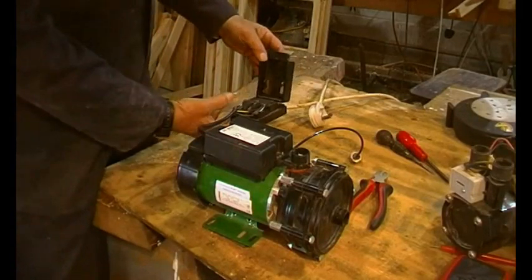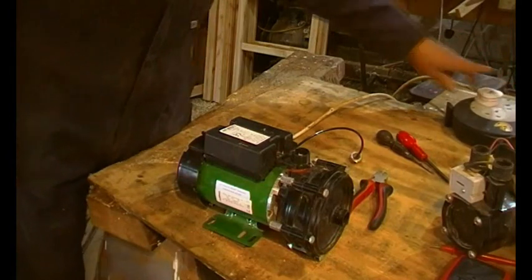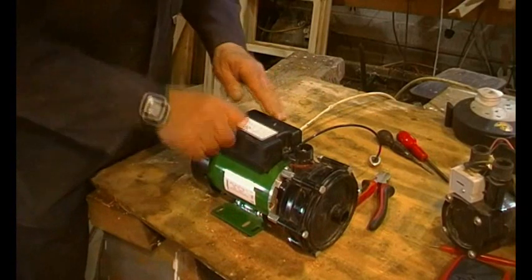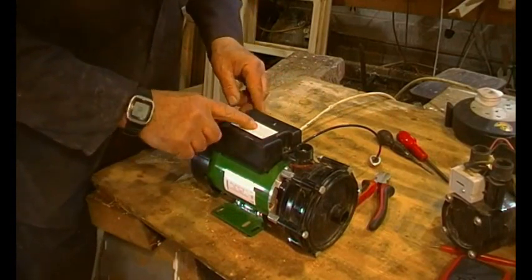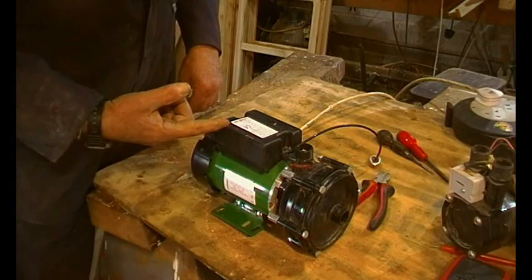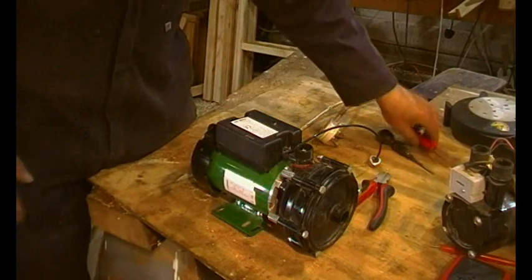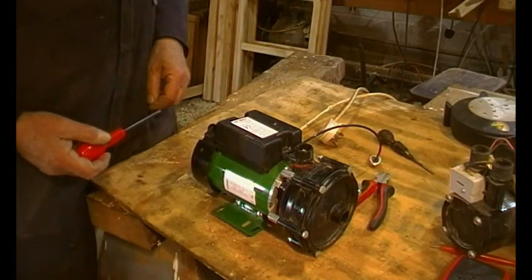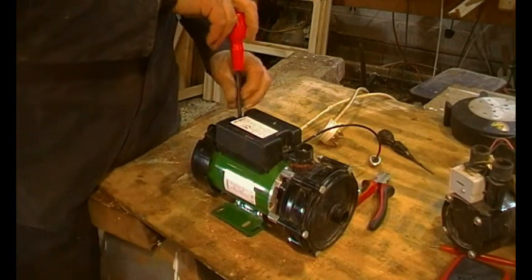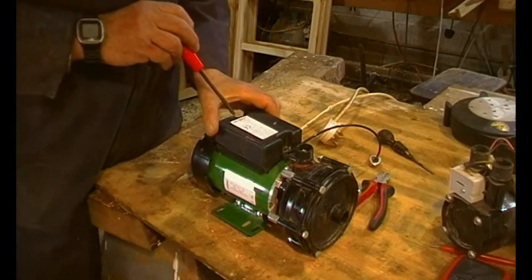I've got the safe block connected — it's not plugged in yet. We'll plug it into the mains and it's just humming, then it stops. There's some electronics in here because there are lights flashing, showing an N and a two, and it's trying again. So it was trying to start but couldn't. Most of us know what that is. By the way, this is a Salamander pump — the ESP 80 CPV.